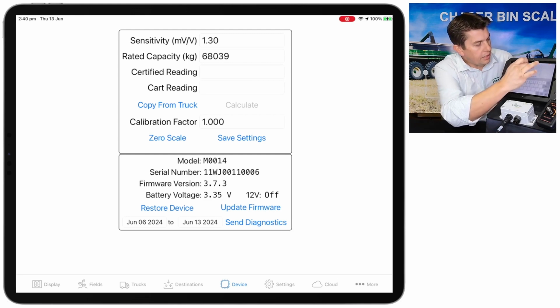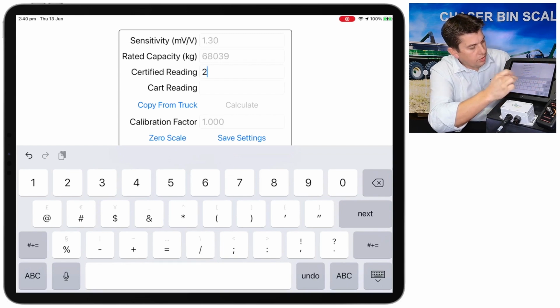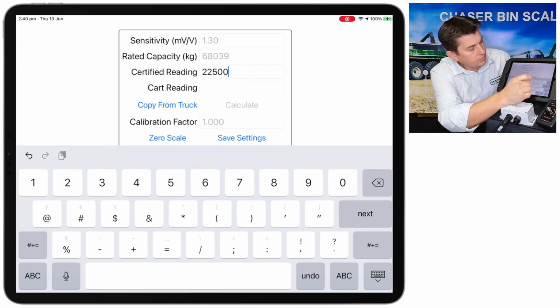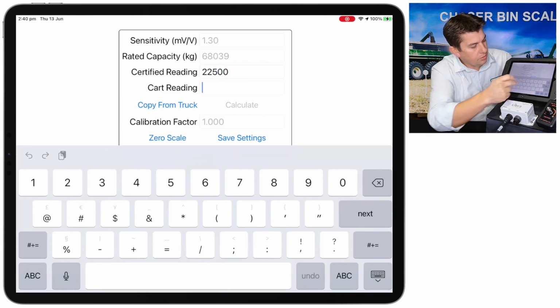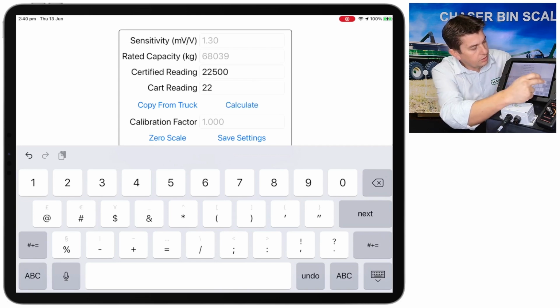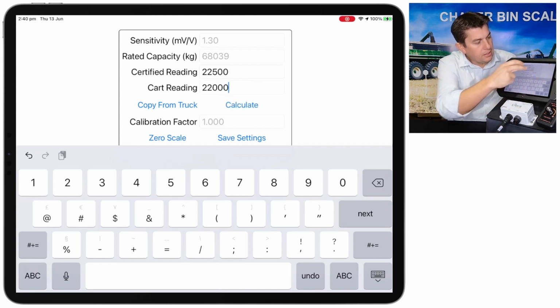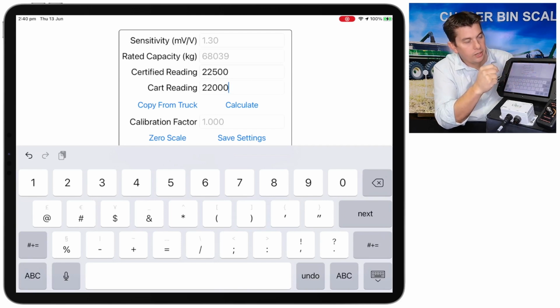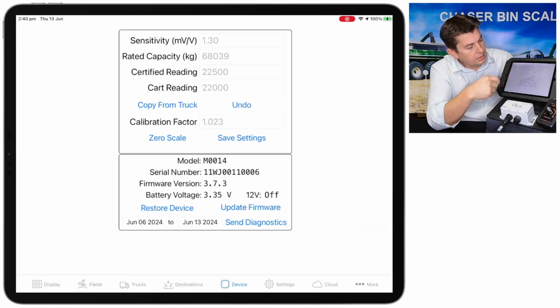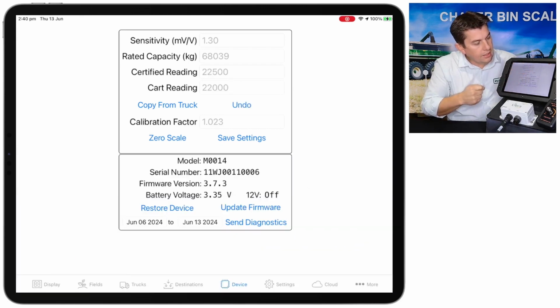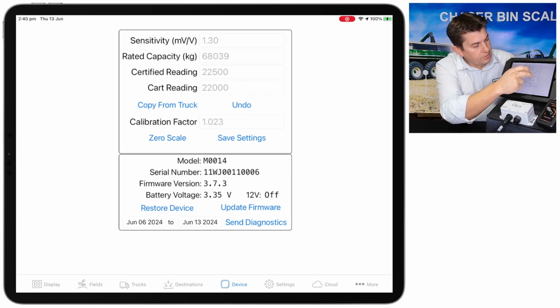So just say we sent the truck over the weighbridge and it said we had 22,500, but the chaser bin said we only had 22 tonne on. So we hit calculate, and just before I do that, you'll notice the calibration factor is 1. When I hit calculate, it'll change that number. So it's just adjusted that calibration factor, and all the numbers are greyed out until we save them settings.